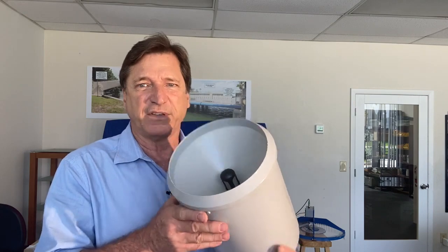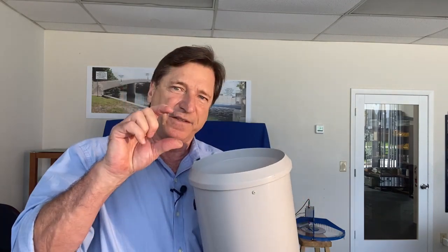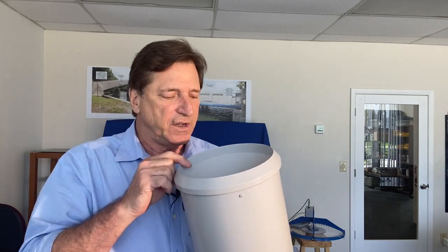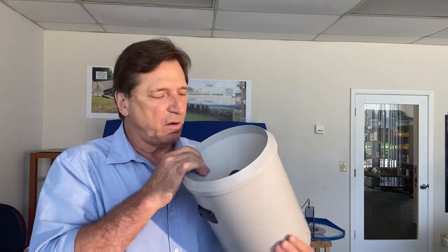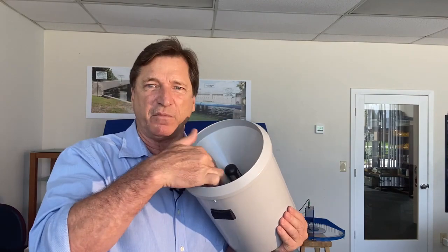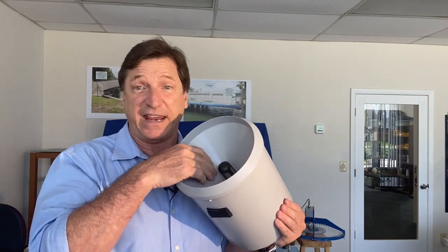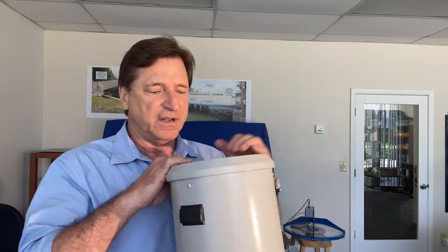So what we have here is a vertical finger filter assembly. This is about 2.5 inches to 3 inches tall. If there is airborne debris blown into the gauge, or bird droppings, it will sit at the bottom and form a false bottom, but it will not impede the entry of rainfall. This is a really, really important feature. The finger filter is very easily removed for servicing.